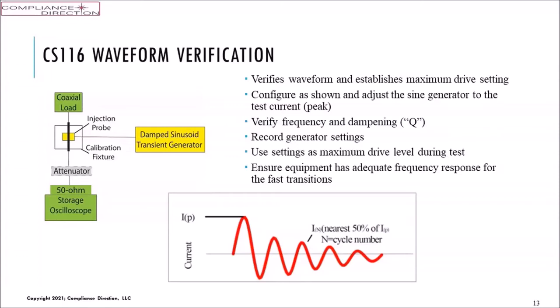So our generator into this calibration jig validates that Q. If the Q is very short, in other words, we don't get much ringing at all, we tend to have an impedance mismatch. If we get ringing that goes on forever, it's a different form of impedance mismatch: a low impedance because it dampens quickly, or a high impedance because we fail to dampen.